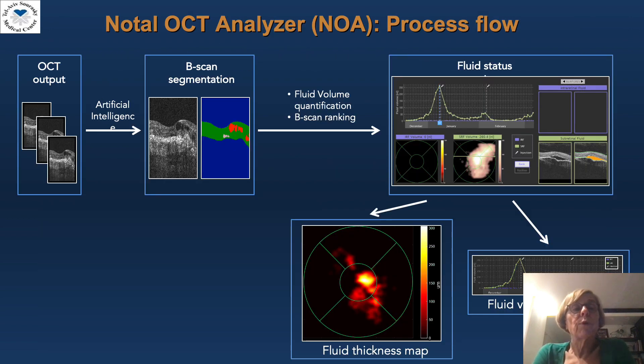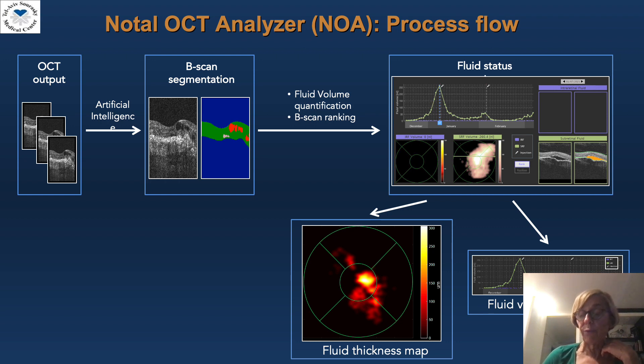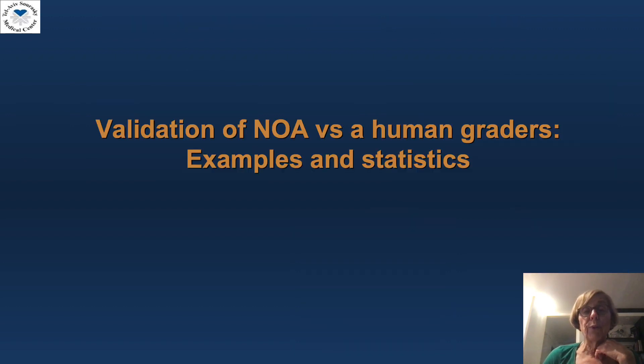This is the process flow of the NOTAL OCT analyzer. The OCT output, the B-scans, are analyzed by artificial intelligence to provide segmentation, fluid volume quantification, and B-scan ranking, as you can see on this fluid status map, which includes both the fluid thickness map and the fluid volume graph.